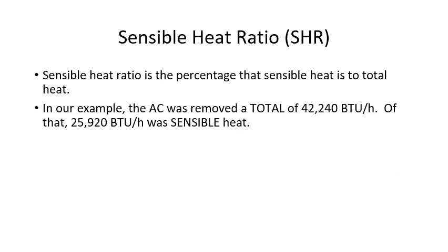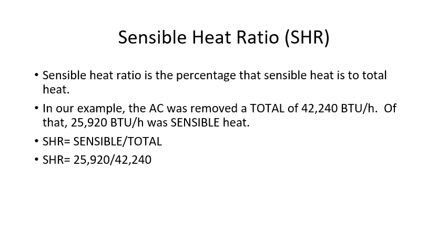In our sample unit, the air conditioning system removed a total of 42,240 BTUs. Of that, 25,920 was sensible heat. The sensible heat ratio is calculated by sensible heat divided by total heat — a very simple formula. In this case, we divide 25,920 sensible by 42,240 total heat, and we arrive at 0.61.